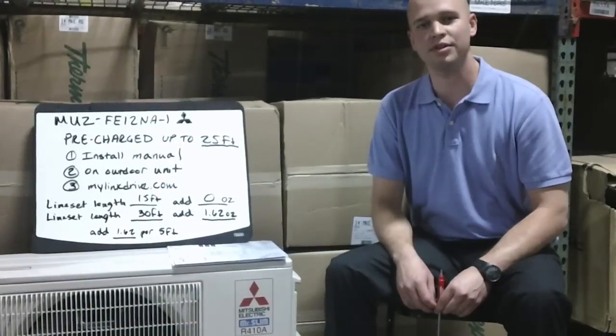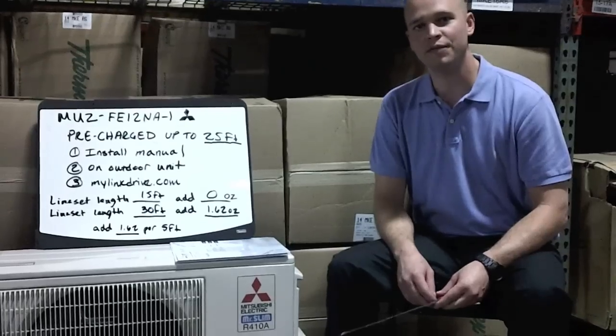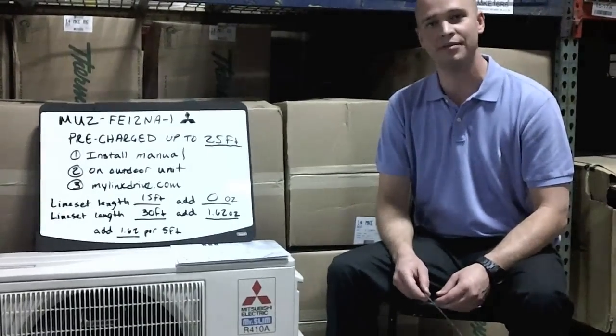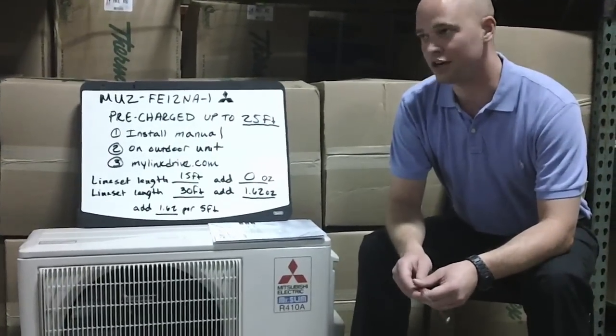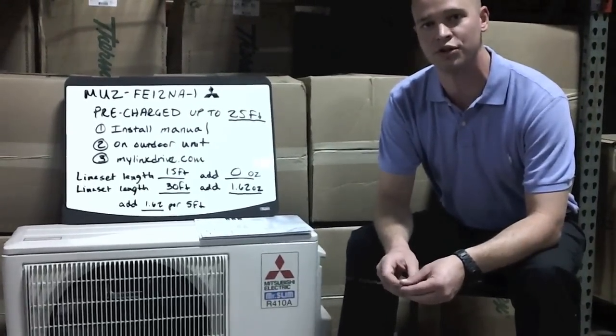Hi, I'm Rob Hayes with Standard Supply and today I'm going to show you how to properly charge a Mitsubishi outdoor condenser. The first thing you need to do to figure out what your charge is on your outdoor condenser is figure out what model number you have. Today we have the MUZ-FE12NA-1, and there are several places where you can find the information on the charge on your unit.